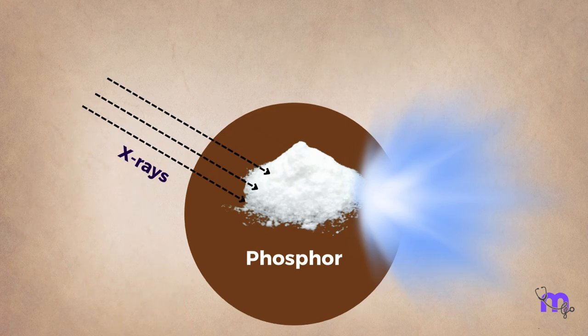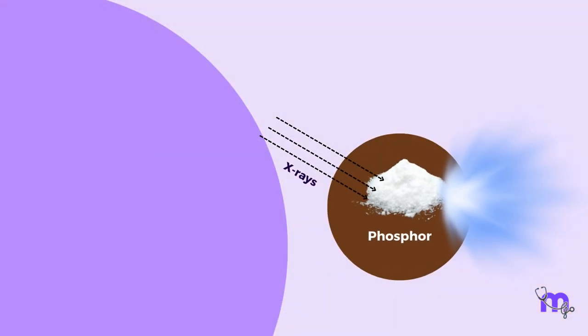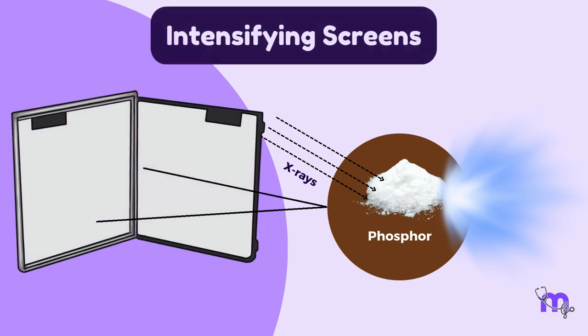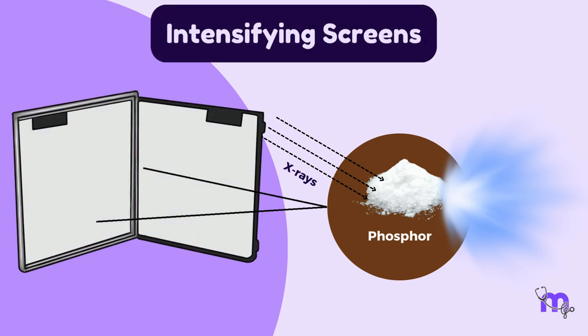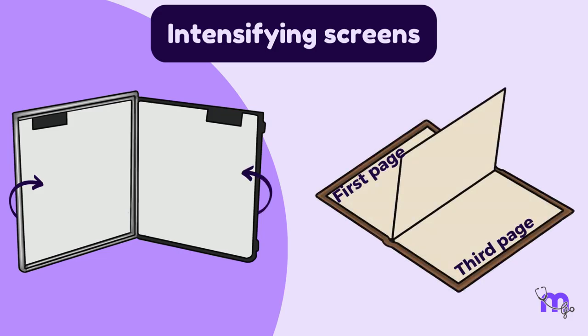It was observed that the intensity of this fluorescence was proportional to the X-ray energy. Coming back to the present, intensifying screens are devices that contain phosphor, converting X-ray energy into visible light. The intensifying screens are installed inside the front and back covers of the cassette, much like the first and third page of the book being stuck to the front and back cover of the book.